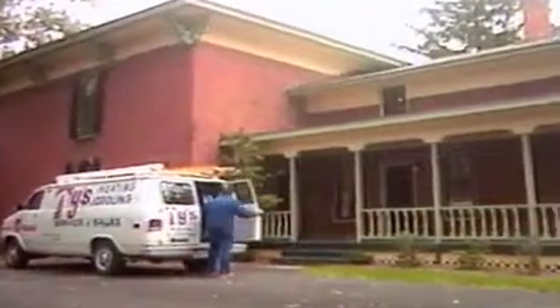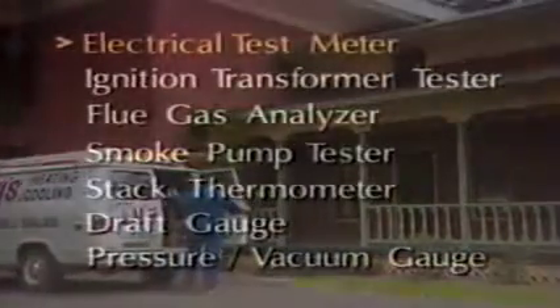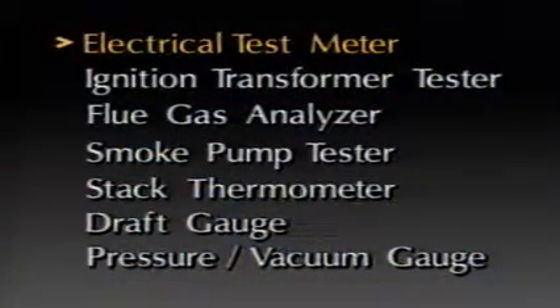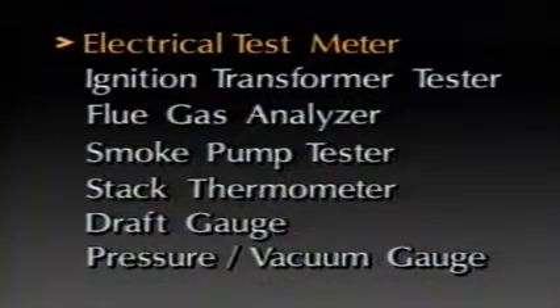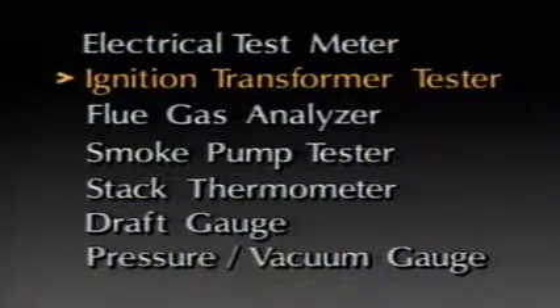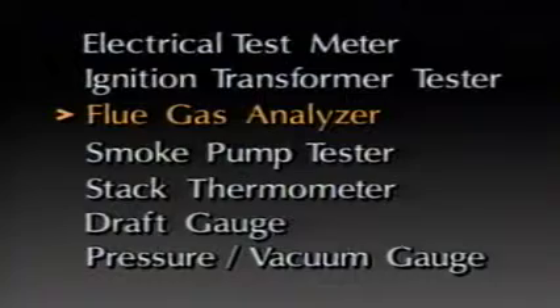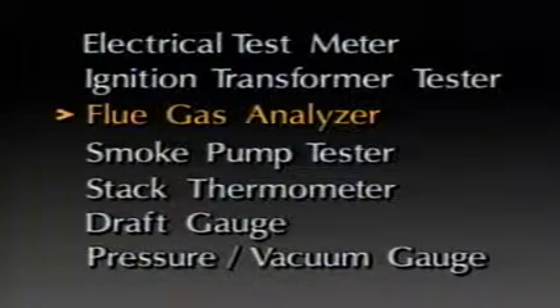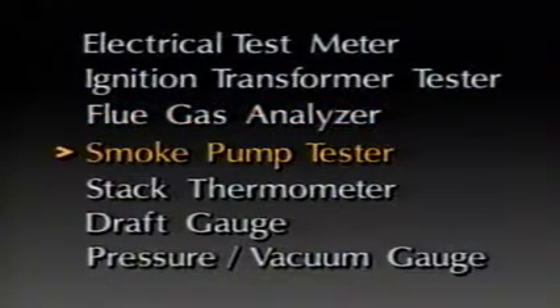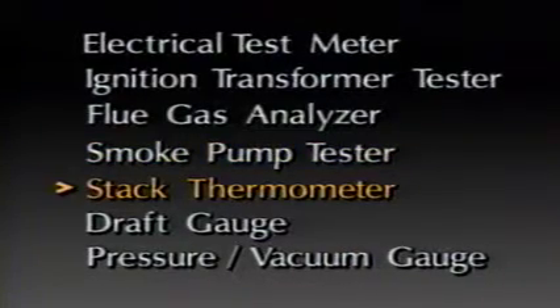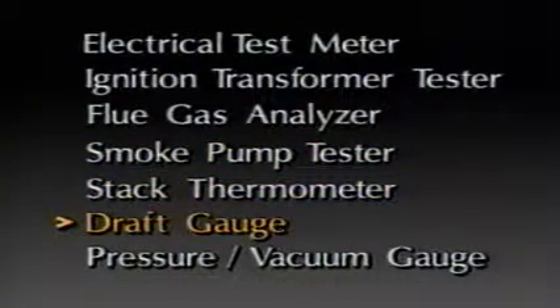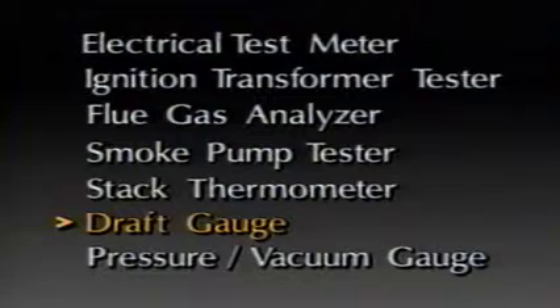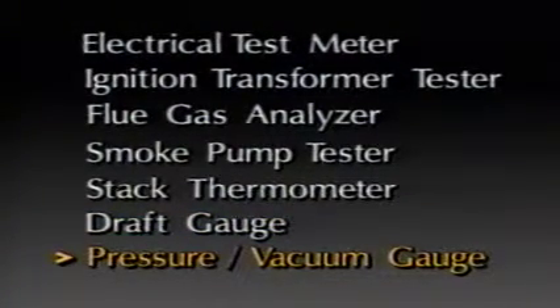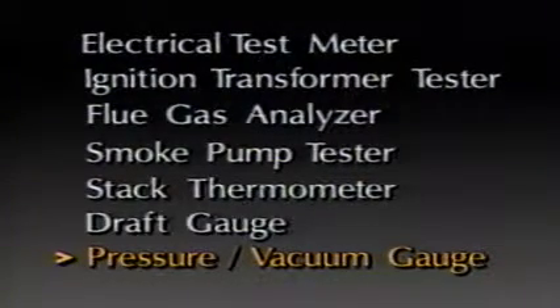Make sure you have the right instruments for the job. You'll want to have an electrical test meter that can measure volts, ohms, and amps, an ignition transformer tester, a combustion flue gas analyzer to measure oxygen or CO2, a smoke pump tester, a stack thermometer, instruments to measure draft and system efficiency, and a pressure vacuum gauge with a scale for 0 to 300 pounds per square inch and 0 to 30 inches mercury vacuum.